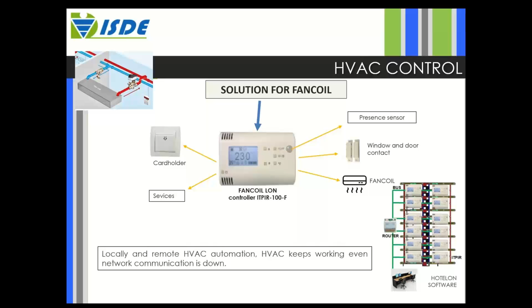It's also important to mention that all LonWorks devices suggested to control the terminal units work locally, and they are also in a network. That means intelligence is distributed across the network, not centralized. This also means that if network communications go down, the whole system in the room keeps working for the user—an important thing to keep in mind.